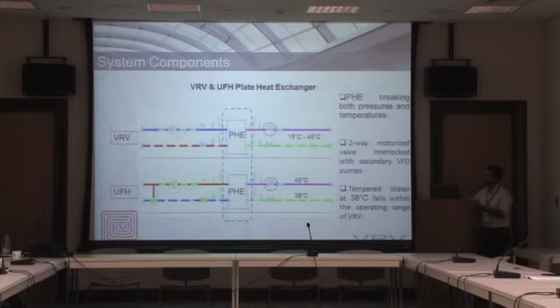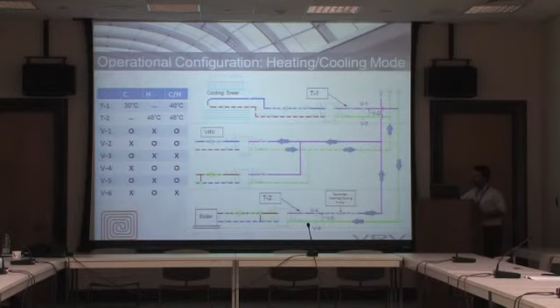This is what I was talking about. The tempered water at 38 falls within the operating range of the VRV, which is between 15 and 45 degrees. This is the operational configuration. During cooling, T1 is set at about 30 degrees. What will happen when T1 exceeds 30 degrees? V1 and V3 will open, V2 will close, V4 and V6 will close and V5 will open. The circulating pump will circulate the water through the VRV.